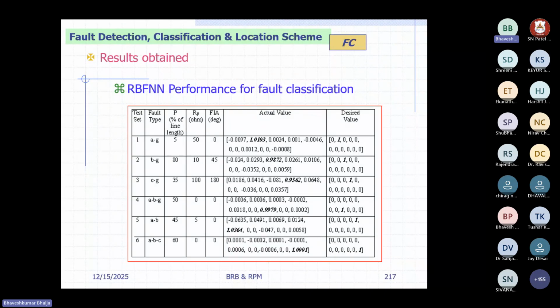Now you can see the first row. There is a test set, AG ground fault. It has occurred at 5% of the line length from the local side or sending end. Fault resistance I have considered 50 ohm. Fault inception angle 0 degree. And the actual value is this one, which I know, and the desired value is this one. So by taking the difference, you can calculate the error also. What is the mean square error?